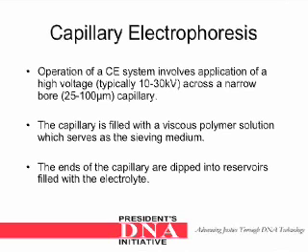Operation of a capillary electrophoresis system involves application of a high voltage, typically 10 to 30 kilovolts, across a narrow bore 25 to 100 micrometer capillary. The capillary is filled with a viscous polymer solution, which serves as a sieving medium.